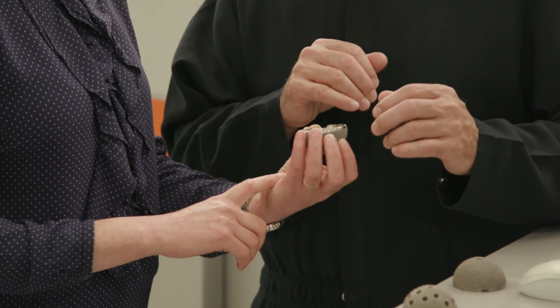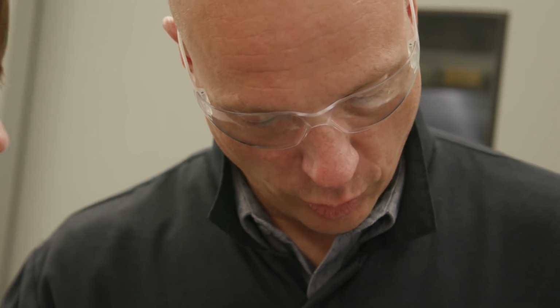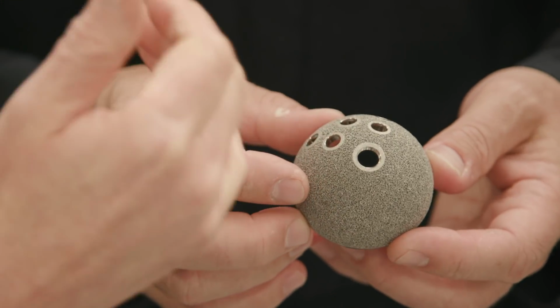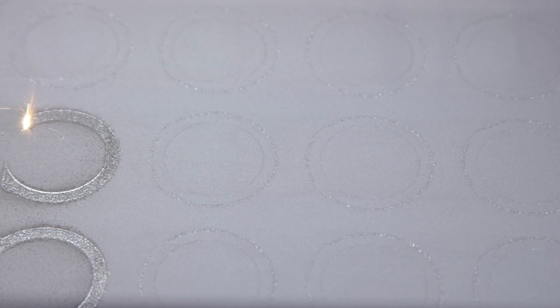Stryker and other companies using additive manufacturing say newer techniques, like in-process monitoring, may prove effective too. So a lot of the machines you see nowadays, you can take images of the build as it's being performed, and you can potentially start to use some of those images as verification methods at the end of a build to make sure that everything within that build has worked successfully. So there is potential with additive because you have the flexibility and you're actually manufacturing that material layer by layer to be able to perform this analysis and hopefully at some point in the future be able to implement that as a verification of the process at the end.